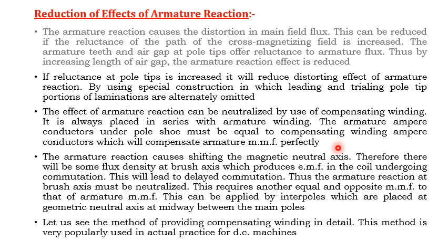Interpoles are placed at the geometric neutral axis, midway between the main poles. These interpoles provide the opposite MMF to that of the armature MMF.